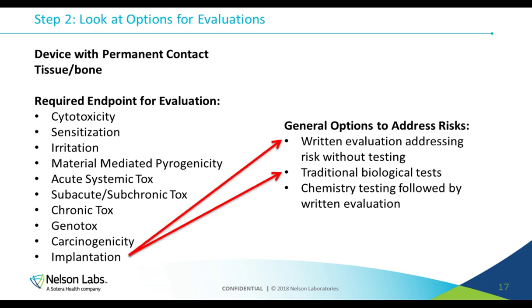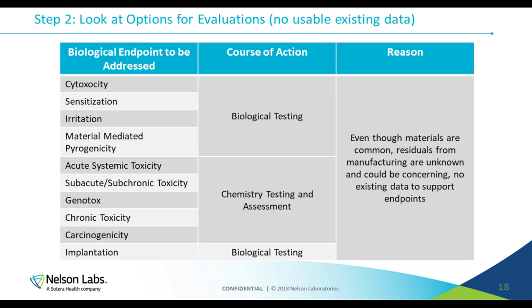For implantation testing, you really have two options. If it's a very well understood material, you can do a written evaluation. Otherwise, you're going to end up doing an implantation test, usually something like a 13-week rabbit implantation. So for this particular manufacturer, when we had gone through all of these details, talking to them at first, they thought that they had a lot of good information on their materials and how clean it was.